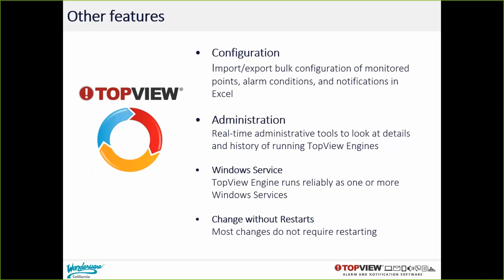The TopView engine runs reliably as one or more Windows services to provide continuous execution regardless of the logged on user. And as I mentioned, typically for larger installations, users will break up the TopView engine into multiple engines that run side by side, each doing a part of the whole. It simplifies configuration, it distributes the load across multiple engines, and allows you to take a single engine up or down without affecting the others. Most systems require change, and with TopView, we've minimized the disruption caused by changes by dynamically applying most of your alarm and notification changes without you needing to restart the TopView engine.